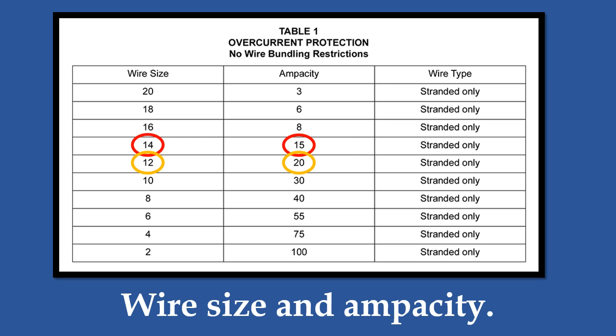This is standard overcurrent protection based on the ANSI RVIA low volt standard and should be used on all RV low voltage systems. Remember, if a listed piece of utilization equipment, say an LED awning light, provides manufacturer's installation instructions specifying that more overcurrent protection is required than that specified in the low volt standard, the manufacturer's installation instructions must be followed. Also remember that the gauge size of the wire on any overcurrent protection device can always be larger than that detailed in these tables, but it can never be smaller.